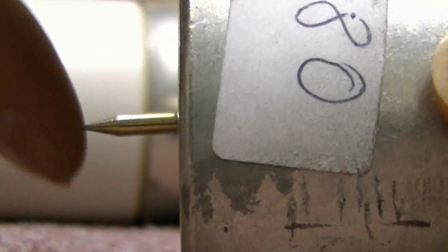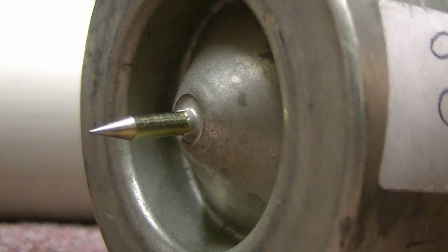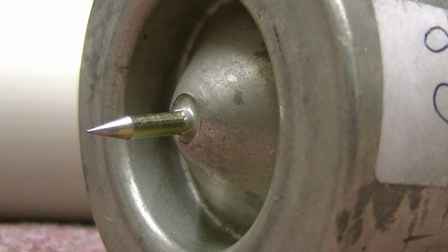It's quite sharp. So yeah, that ID's when the fuse is actually gone, and trips out any remaining phases that have not tripped. And that's all that does. 80 amps that way. It takes about 3 times rated current to actually pop that.